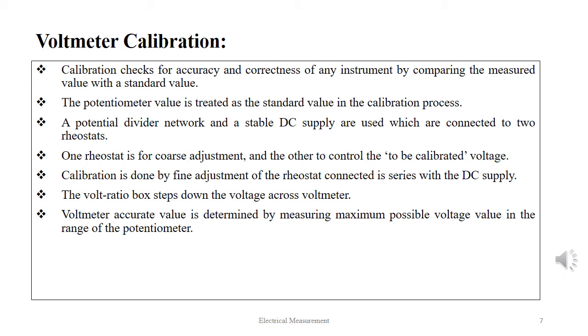A potential divider network and a stable DC supply are used, connected to two rheostats: one for coarse adjustment and the second for fine adjustment. Calibration is done by fine adjustment of the rheostat connected in series with the DC supply. The volt ratio box steps down the voltage across the voltmeter so that the range of operation can be specified. The voltmeter's accurate value is determined by measuring the maximum possible voltage value in the range of the potentiometer.